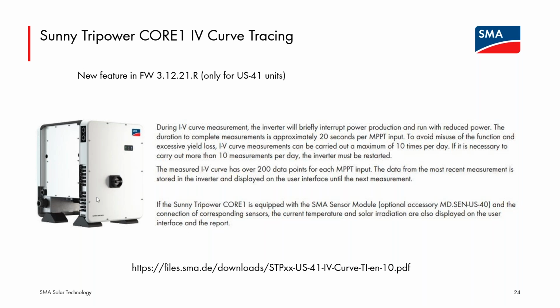So without having to shut the system down, without having to tear apart the array, remove any module level power electronics, or put all the modules in series to do an IV curve trace, you can have the system wired as it is during operation, trigger the IV curve trace, and then be able to archive those curves year after year to be able to benchmark performance.